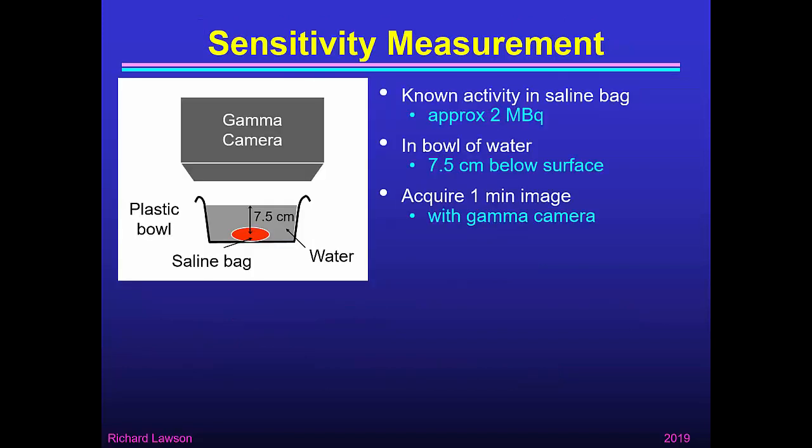To measure system sensitivity, we just need a phantom. I like to use a saline bag which is roughly kidney-sized, and inject into it a known activity of technetium-99m solution — about 2 megabecquerels is sufficient. I place it at the bottom of a bowl of water with 7.5 cm of water from the centre of the bag to the surface, to simulate the depth of the kidney in a patient's back. The water is a good substitute for human tissue because it has about the same attenuating factor. Then place the bowl with the saline bag underneath a gamma camera looking down at it and acquire a one-minute image.